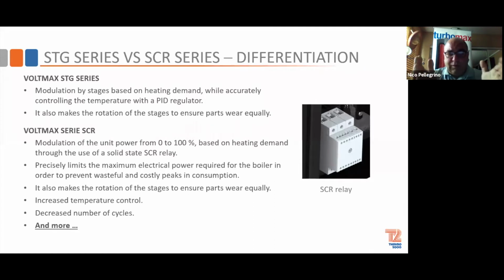So that's only available in the 180 version. So 180 and under, you can get either STG or SCR. Now the big 400 is all SCR control. SCR means that we modulate the elements from 0% to 100%, a bank of elements. Depending on the size of the boiler, there's always going to be one bank of elements that is going to stage from 0 to 100%. So basically, it gives you a modulating effect on the boiler system.